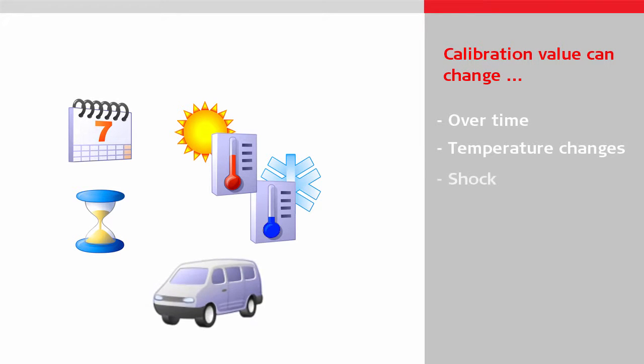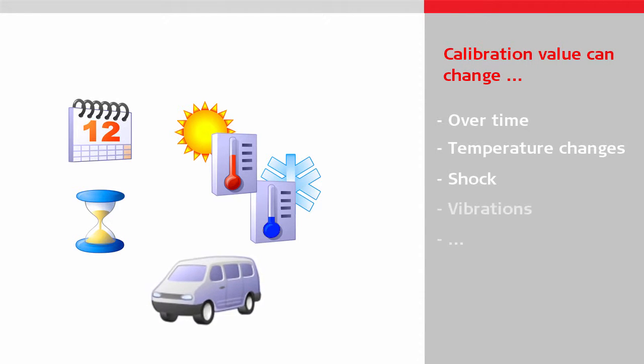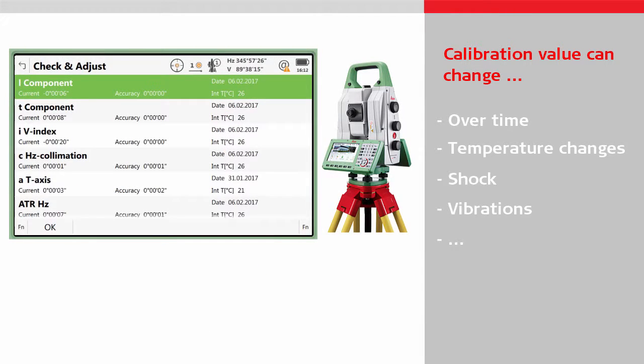Over time, stress due to temperature changes, shock, vibrations, etc. means that the errors and therefore the correction values have to be redetermined from time to time to guarantee the best measurement performance.